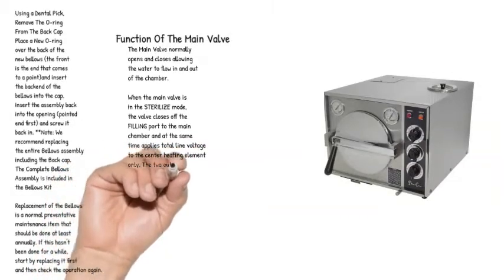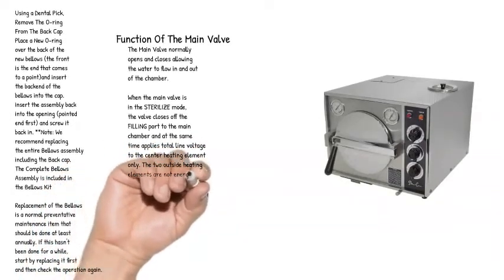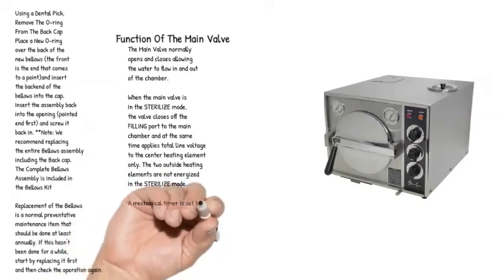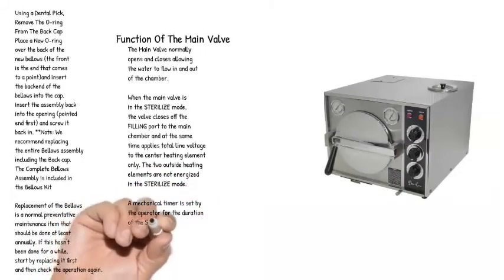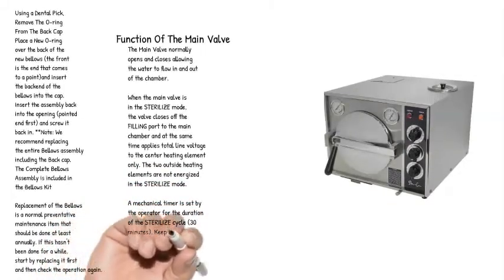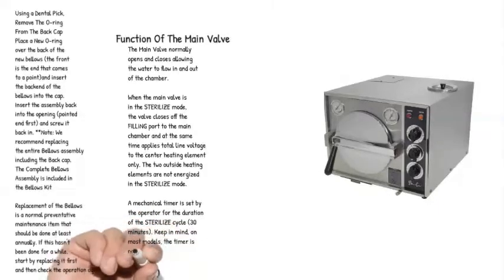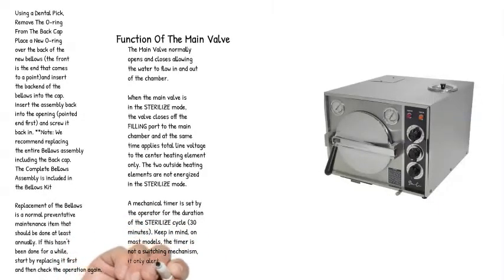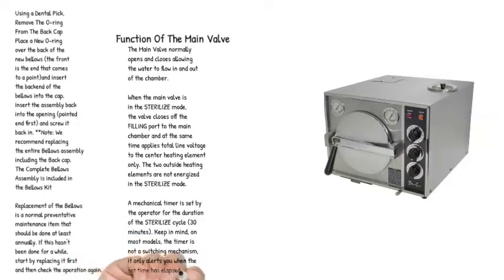The two outside heating elements are not energized in the sterilize mode. A mechanical timer is set by the operator for the duration of the sterilize cycle, 30 minutes. Keep in mind, on most models, the timer is not a switching mechanism, it only alerts you when the set time has elapsed.